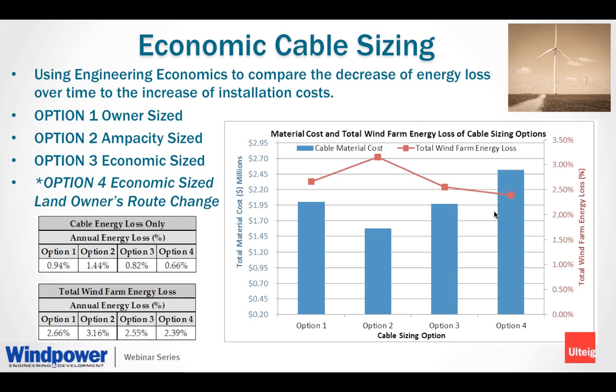So we had to do some adjustments there, and it's kind of neat to see the results on this slide here. The cable energy losses only, and this is just the losses on the cable, are shown in the chart on the upper left. You can see that option 4 has the least amount of cable losses. However, if you look on the bar graph, it actually costs the most to install. And if you look at the complete opposite, the one that's the cheapest to install, option 2, has the highest losses. So what I'm trying to get at is, how do you compare losses versus installation costs over time?